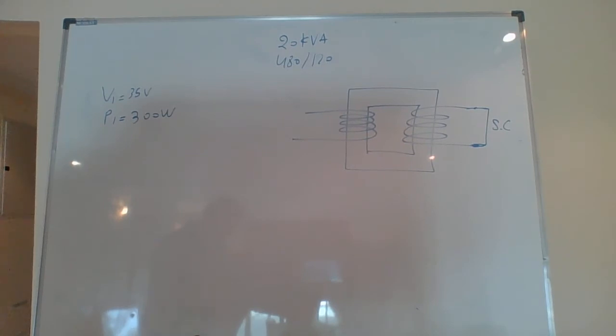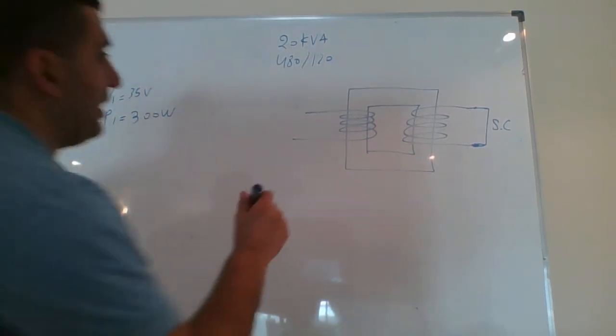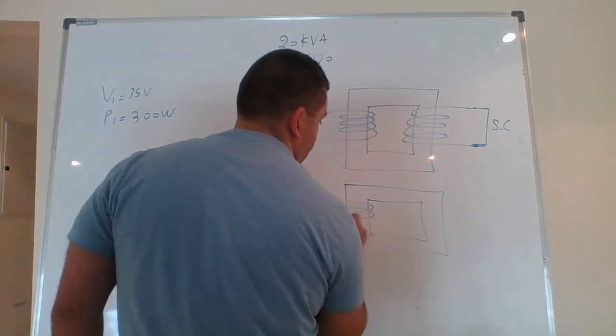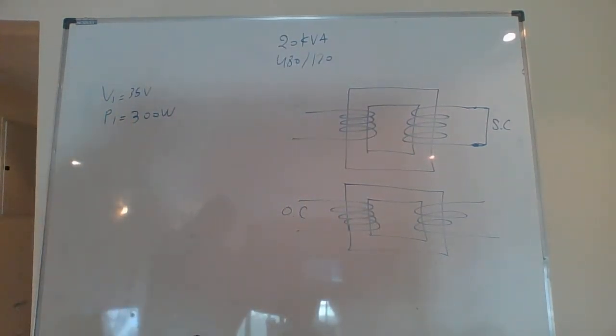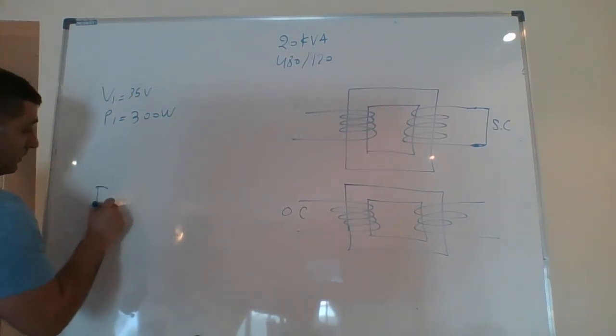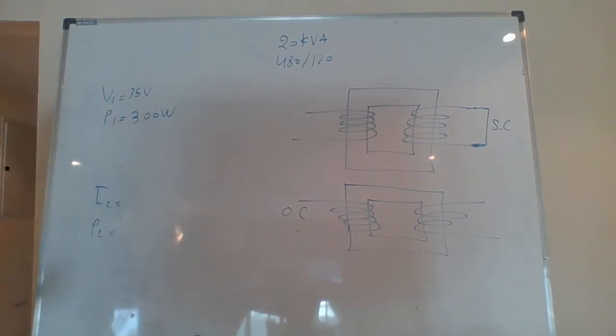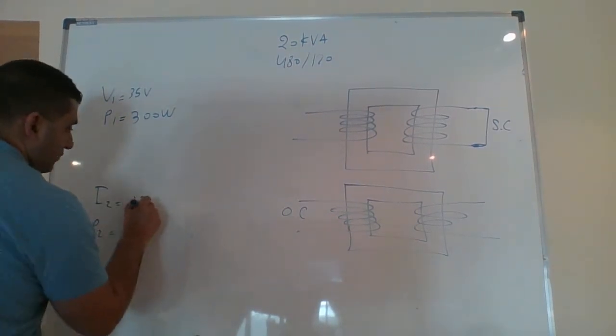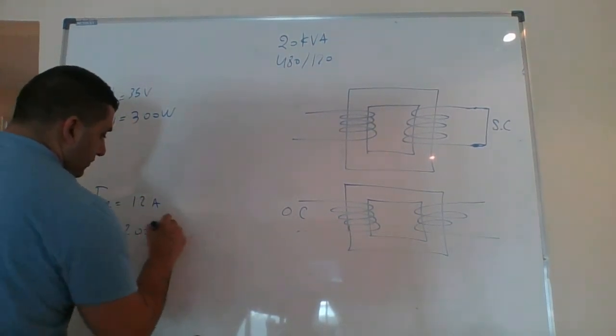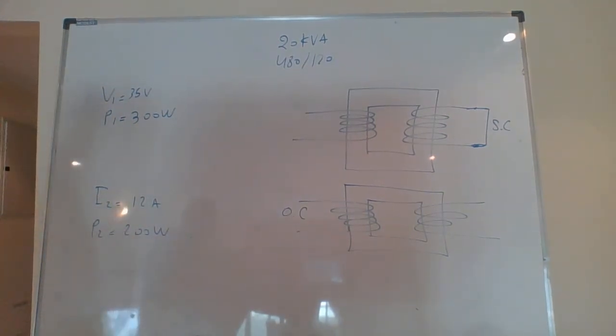During an open circuit test, where rated voltage is applied to winding two with winding one open, the following readings are obtained: I2 equals 12 amps and P2 equals 200 watts.